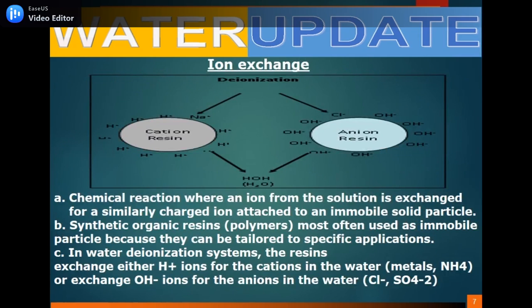The next method is ion exchange. Ion exchange is a chemical reaction where an ion from solution is exchanged for a similarly charged ion attached to an immobile solid particle. Synthetic organic resins are most often used as the immobile particle because they can be tailored to specific applications. In a water deionization system, the resins exchange either H+ ions for cations in the water, or OH- ions for anions in the water.